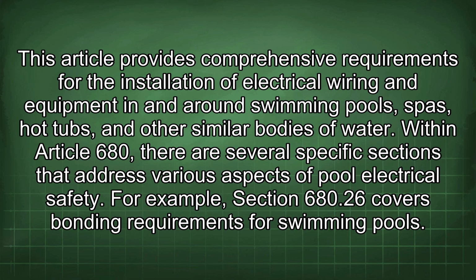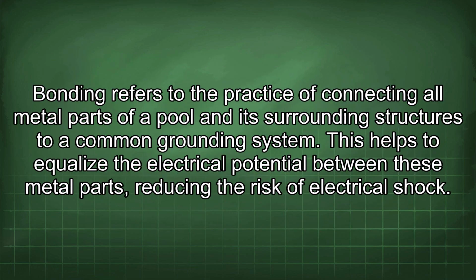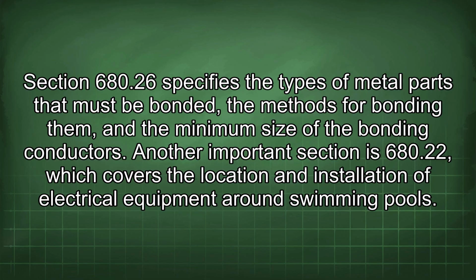For example, Section 680.26 covers bonding requirements for swimming pools. Bonding refers to the practice of connecting all metal parts of a pool and its surrounding structures to a common grounding system. This helps to equalize the electrical potential between these metal parts, reducing the risk of electrical shock. Section 680.26 specifies the types of metal parts that must be bonded, the methods for bonding them, and the minimum size of the bonding conductors.